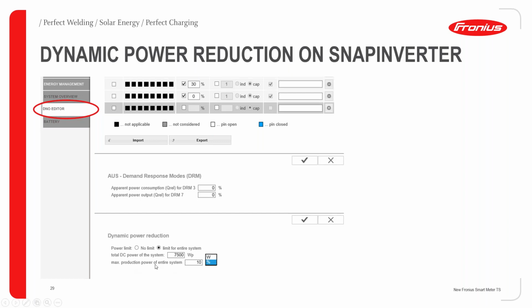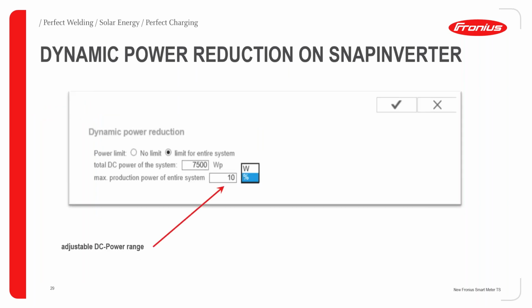Then the maximum production power of the entire system, you can limit either by percentage or by watt. You can say you want to limit 10%, only feed in 10% of the system. For example, in case of Germany, it's very simple. You don't have to calculate about the amps or wattage. You can simply put 70% here. So the maximum power production of the entire system will be limited to 70%, that's the feed-in limitation. Or there is a small calculation for how to adjust it. For example, if you want to adjust it because of fuse rating, if you have a fuse 20 or 63, then based on that, if you want to limit, you have to calculate in watts.